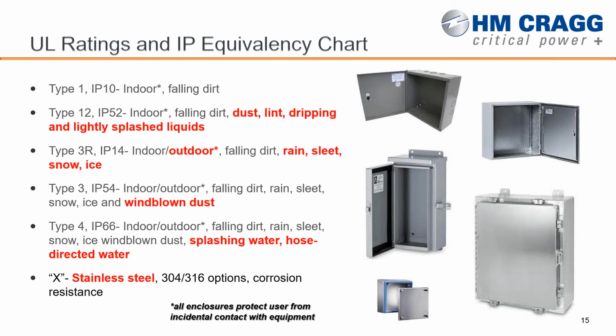I've got a couple comments on this slide really quick. In the industry, you'll hear a lot of terms being thrown out, such as NEMA enclosures or NEMA type enclosures. HM Cragg is specifically focusing on labeling these as type enclosures. That is the key word to know if an enclosure is UL listed. A NEMA enclosure may or may not be UL listed, but if it is labeled as a type enclosure, we know that it's UL listed.